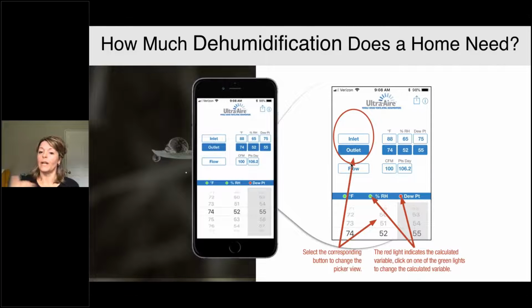The outlet is what I want in my house. I want it to be 74 degrees, 52% relative humidity. And really what I'm going after is that 55-degree dew point. And the flow is how much fresh air my ventilation rate is. So I'm saying that the ventilation rate here is 100 CFM. So this is telling me, based on those conditions, that I'm going to need about 106 pints of water removal a day. This is solely based on ventilation. And then you take in your occupants. So if you have a family of 4, then you're going to have to add that number to this, and it'll give you how much dehumidification you're going to need.